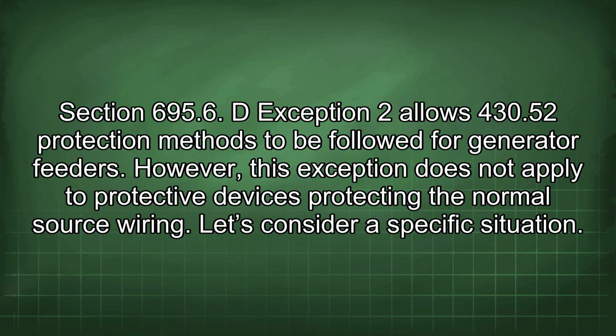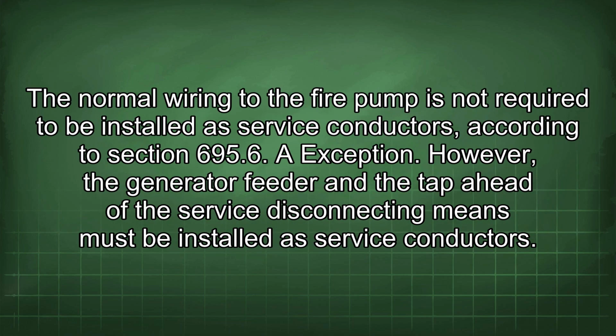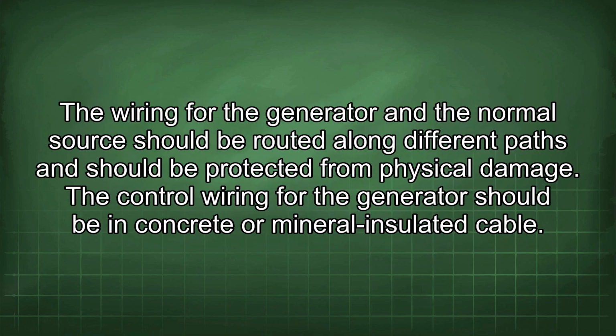Let's consider a specific situation. The normal wiring to the fire pump is not required to be installed as service conductors according to section 695.6, exception. However, the generator feeder and the tap ahead of the service disconnecting means must be installed as service conductors. The wiring for the generator and the normal source should be routed along different paths and should be protected from physical damage. The control wiring for the generator should be in concrete or mineral insulated cable.